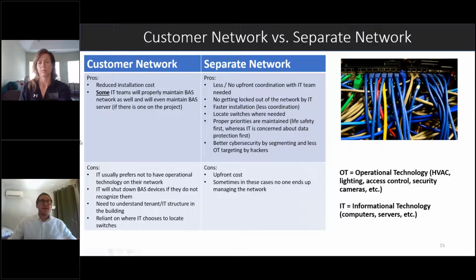So here's the final discussion - sorry, I talked a lot on this one, I get excited about MSTP versus IP. We have a quick comparison of customer network versus separate network. A lot of the information is on the slides, but the main thing I'll point out is that more often than not, from the BAS side of things, we'd prefer to see a separate network used. Unless there's very good upfront coordination with the IT team, and the building IT team is comfortable and familiar with building automation system devices, those are the times you could combine together and leverage the customer's network. But a separate network is probably the right strategy if you don't have the means for that upfront coordination.